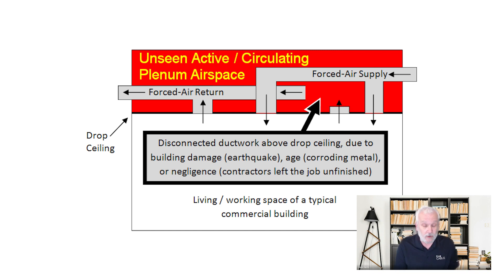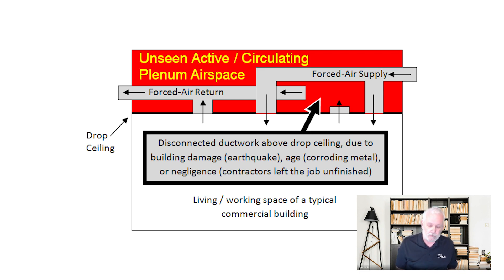Nowadays, the area above a suspended ceiling is often not used as a plenum space — they have enclosed ductwork for the returns, so you don't have to use plenum cable in those cases. However, best practice is to keep in mind that a non-plenum space above a suspended ceiling can easily become a plenum space through unauthorized work, corrosion, earthquake, or other events over the decades a building is in service. So best practice is: anytime you're above a suspended ceiling, use plenum cable.